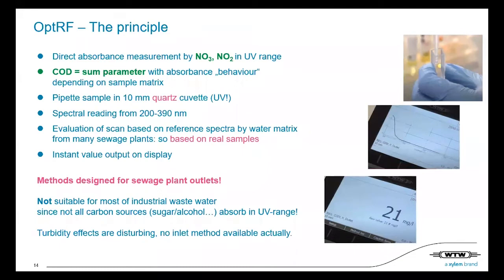Then in the background, there are complex algorithms, and the scan which we have performed is evaluated, and then it is more or less compared to a background, real sample kind of calibration curve. So actually we do have a reference spectra in the background. And once this has been compared, aligned, and evaluated, which takes about 30 seconds, the instant value output for the COD value is displayed.